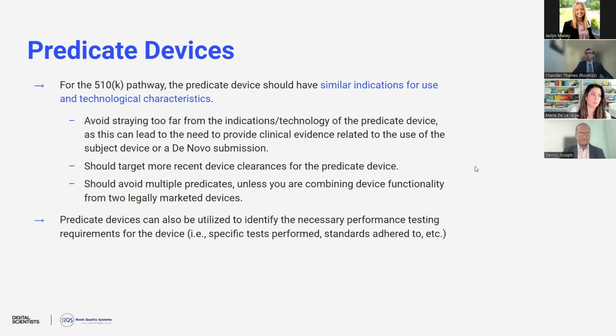Another benefit of predicate device identification is the 510(k) summaries, PMA summaries, and de novo summaries are all publicly available information. So if you're curious as far as what sort of performance testing you would need to subject your device to, or if clinical testing is required, or if there's certain design parameters that you need to account for in your design, you can oftentimes find some of that information, even if it's a little high level, within those regulatory submission summaries. So that can really be a good tool for laying out your roadmap for identifying that performance testing very early on, maybe even before you have a final prototype in hand. Just being aware of what sort of testing you need to subject the device to can really help identify the way that you want to design the device, accounting for that testing.